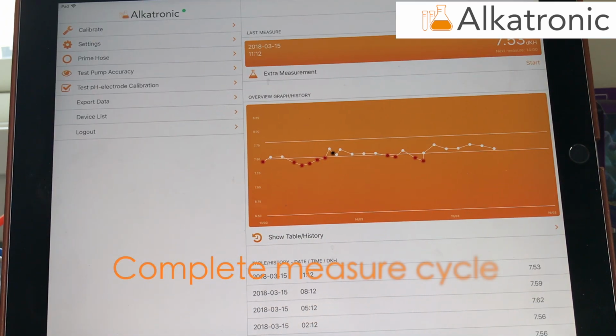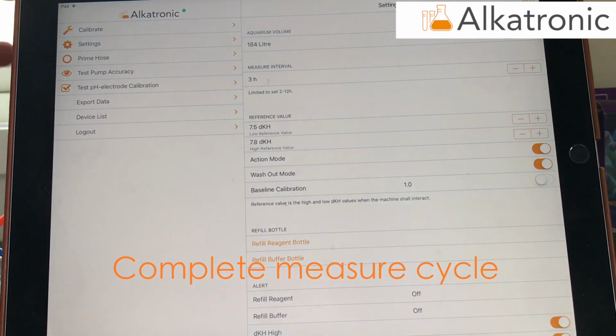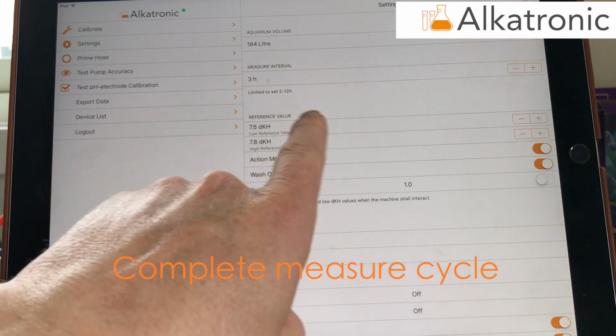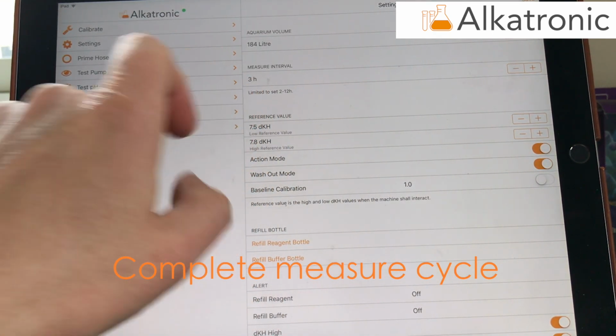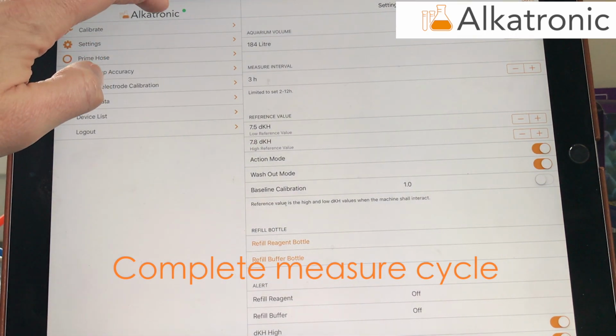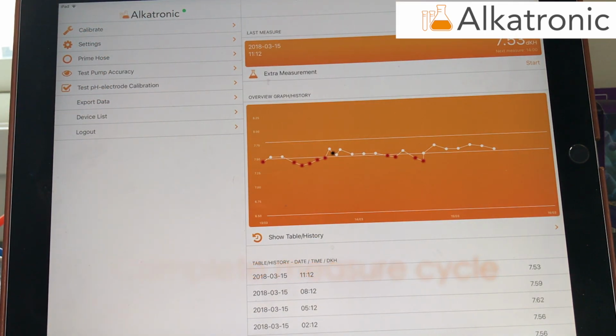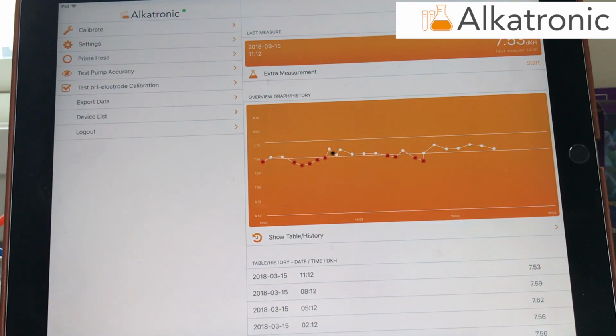Now I want to demonstrate the measure cycle. The machine is of course measuring according to the schedule that you are setting in the settings. Here I have it set so that every 3 hours the machine will do a measurement, but you can of course do manual measurements, extra measurements so to speak, and that you do by pressing start. And then the machine will do an extra measurement, and I will use that to describe a complete measure cycle.